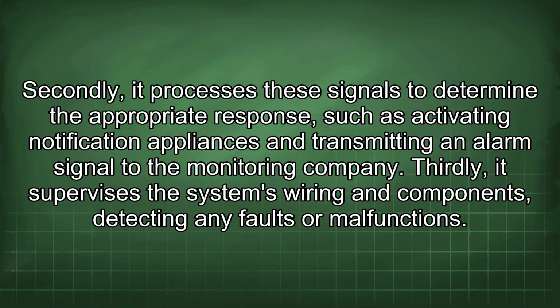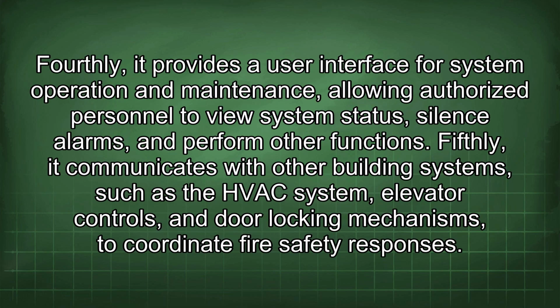Thirdly, it supervises the system's wiring and components, detecting any faults or malfunctions. Fourthly, it provides a user interface for system operation and maintenance, allowing authorized personnel to view system status, silence alarms, and perform other functions. Fifthly, it communicates with other building systems such as the HVAC system, elevator controls, and door locking mechanisms to coordinate fire safety responses.